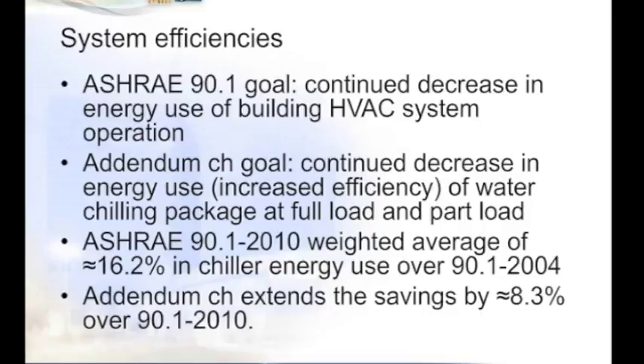But the goal primarily of Addendum CH is a continued decrease in energy use, or increased efficiency, of water chilling packages at both full load and part load conditions. And I think most of it, in Path B in particular, favors the part load condition and how the equipment can be operating at its most efficient and achieving the building goals by doing that. ASHRAE 90.1 2010 noted a 16.2 decrease in chiller energy use over the 2004 edition, and this addendum reduces that even further by approximately 8.3% over the original 90.1 2010 version.